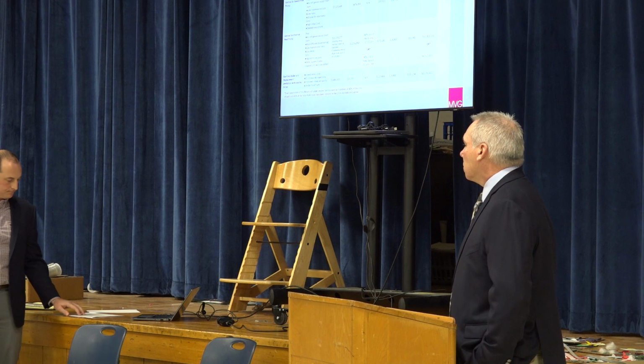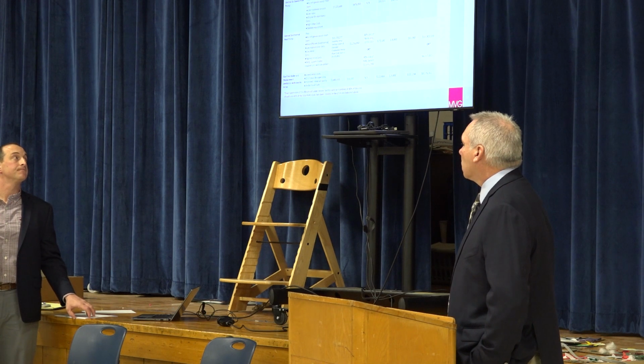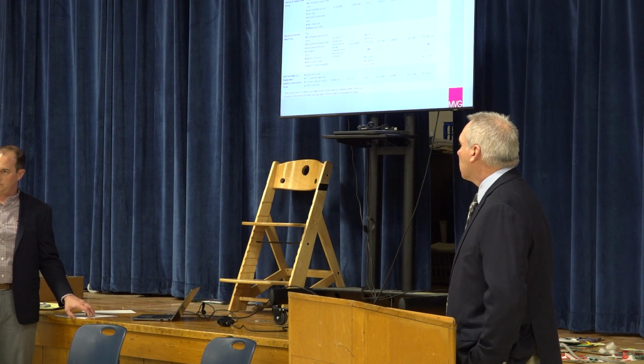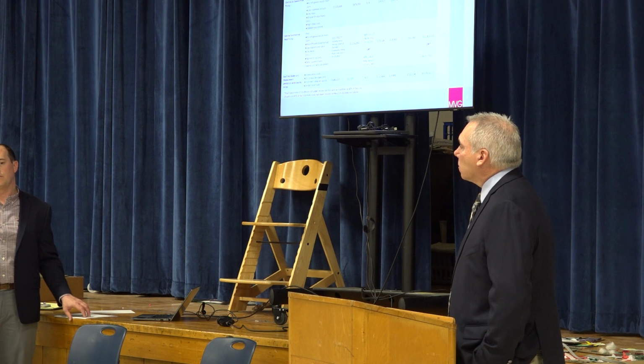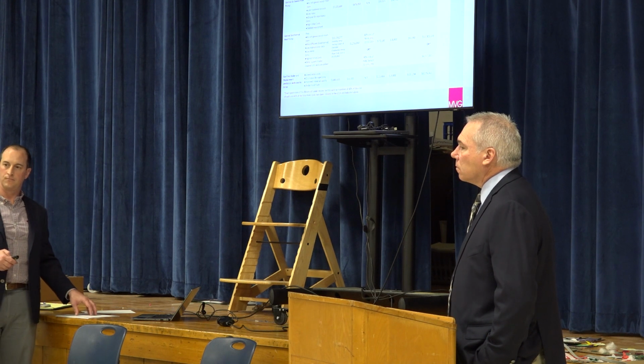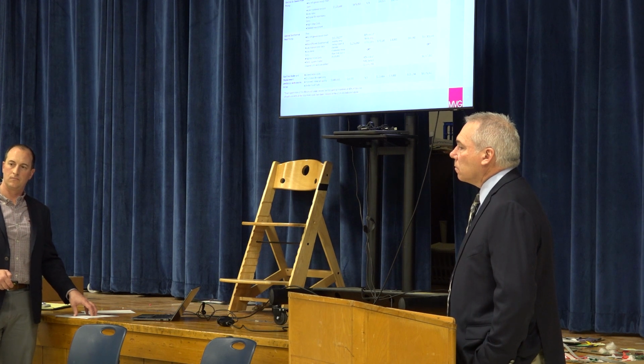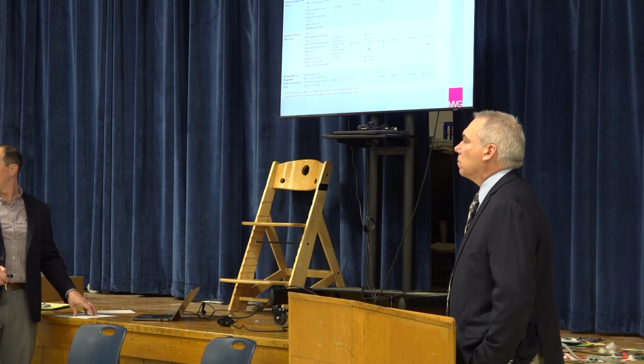Yeah, we were talking about the temporary systems and their impact. You can see two different numbers listed there. For the highest number for the central geothermal system, we're at 10.2 million, which includes the temporary system and the extended construction period based on it. The temporary system has an estimated cost of a little under $100,000. That's not fully accurate, because if you have a temporary system, it means you can't count a lot of events in your 40%, so your cost goes way up, way more than $100,000. The $100,000 was for the temp system, the plans, whether a boiler or something outside to carry the building until completion. That's where that number was coming from.